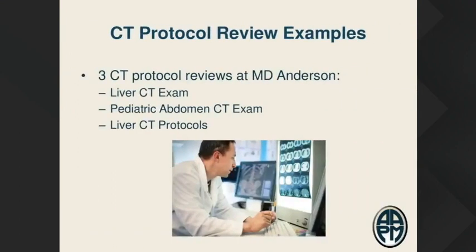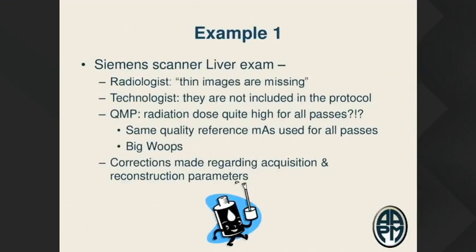Here are a few examples of CT protocol reviews performed at MD Anderson. Example one: a Siemens scanner liver exam. The radiologist was concerned because expected thin images were missing from the exams. The technologist responded that they weren't included in the protocol on the scanner. The physicist noted the radiation dose seemed pretty high for all the multiple passes, having wound up using the same quality mAs for all passes — considered a big error. Corrections were made to both acquisition and reconstruction parameters all at once on this liver exam, illustrating how the team can work together effectively.